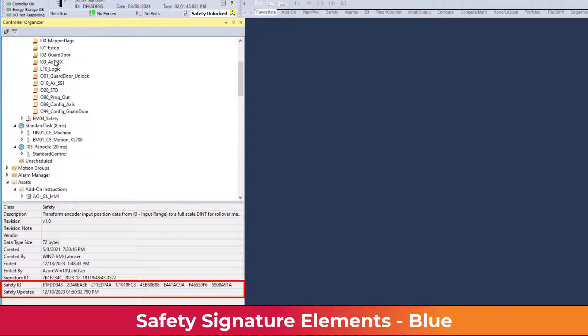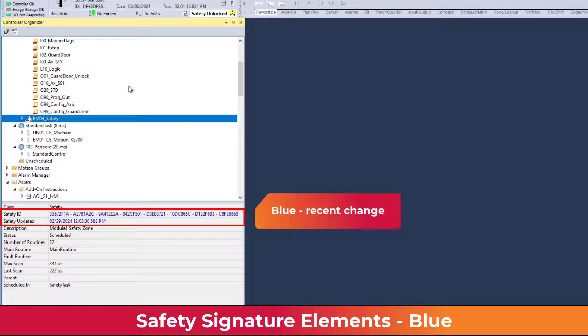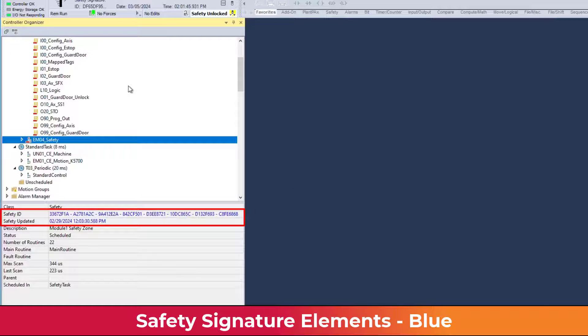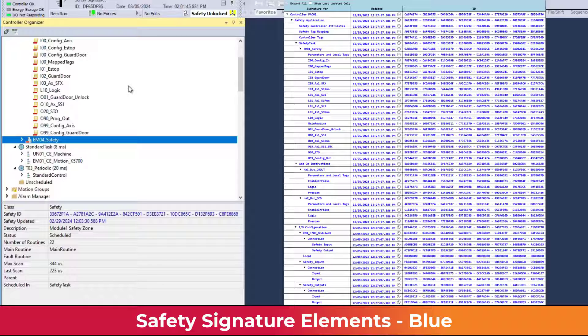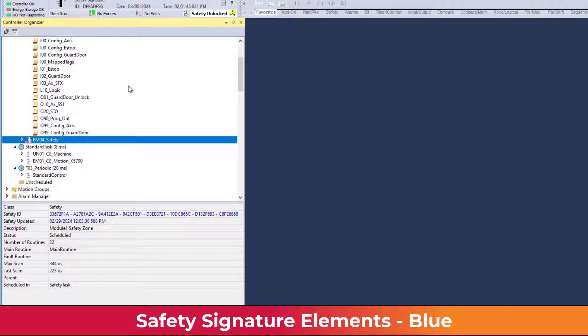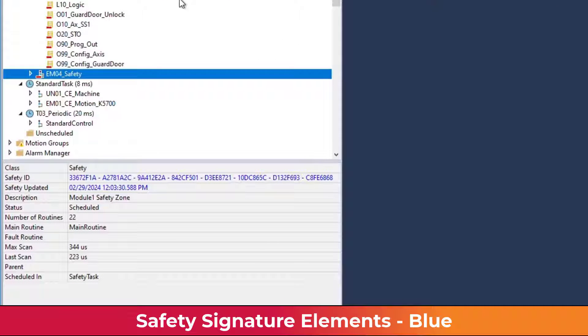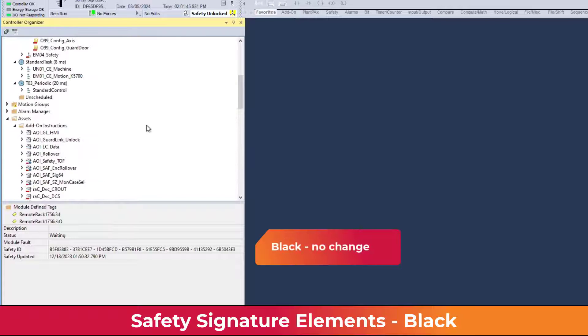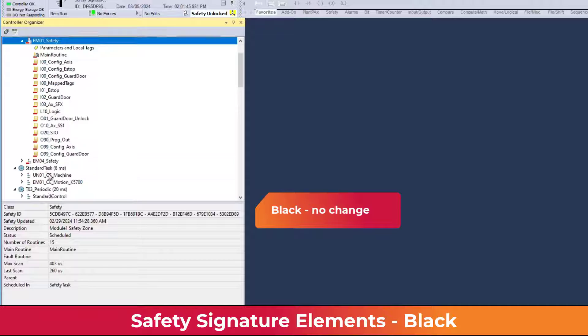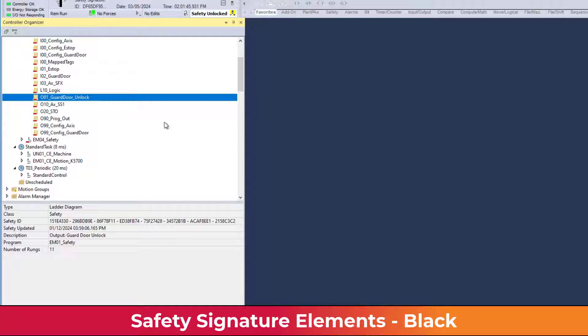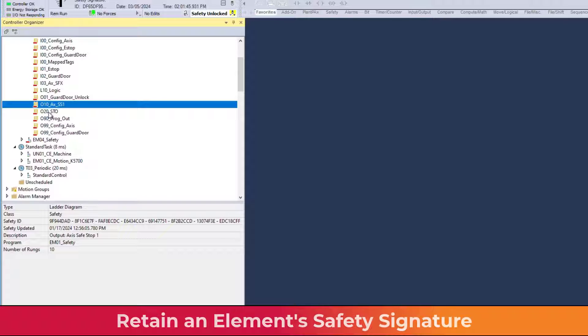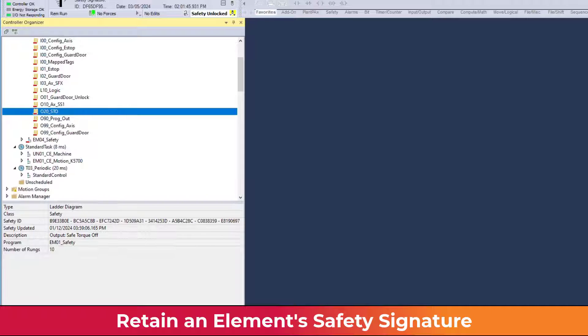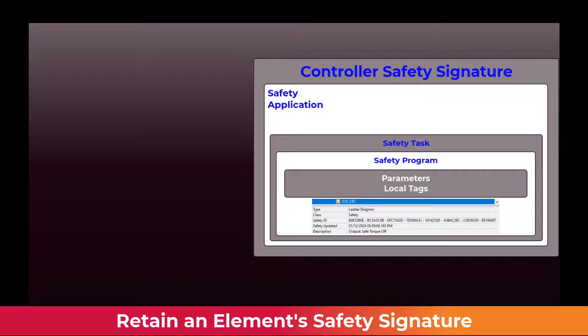The signature elements are displayed in different colors. Blue indicates the most recent signature change. An application converted to firmware version 36 or greater for the first time will display all elements blue after the initial signature generation. When viewing blue signature elements, review the date to determine when the most recent change took place. Safety signatures displayed in black indicate no change. Elements with signatures already in place can be copied into an existing project and retain the signature from the origin file — for example, a routine with no external dependencies can be copied into an application, and when the signature is generated, that element will remain black.